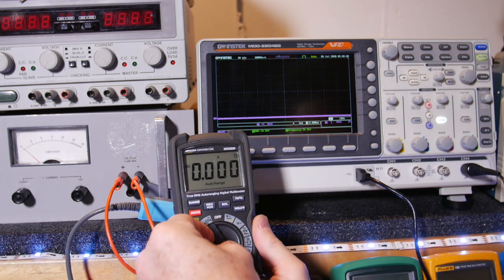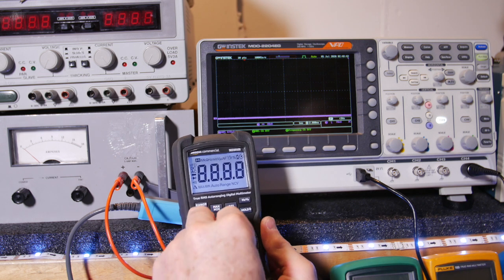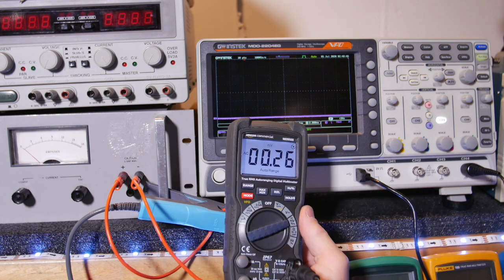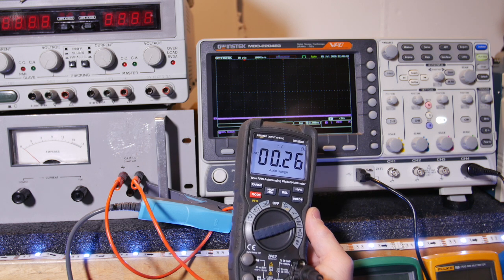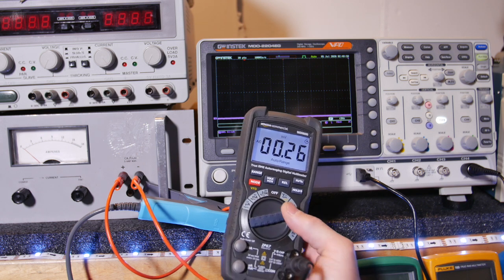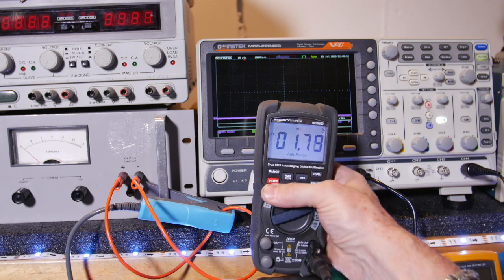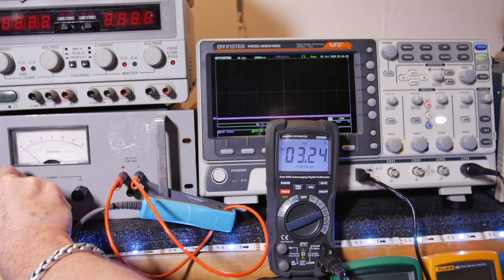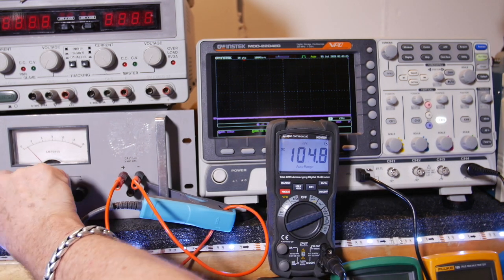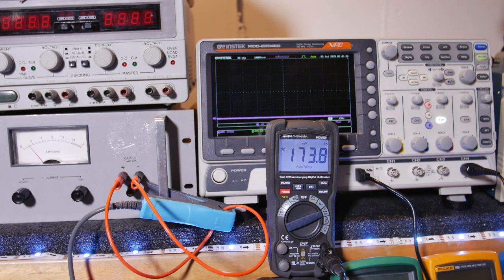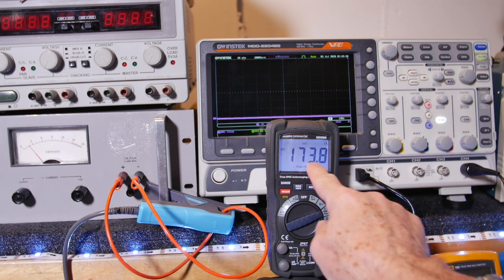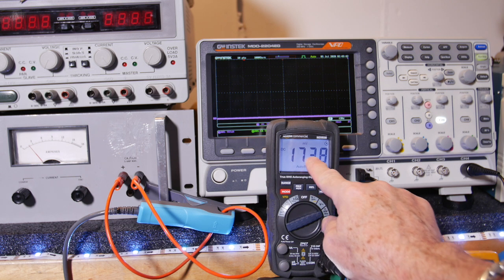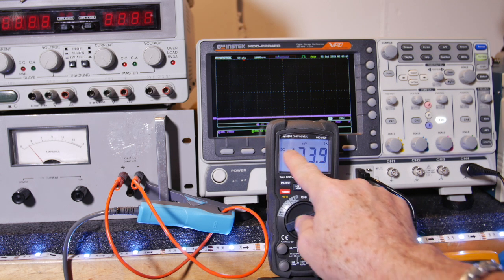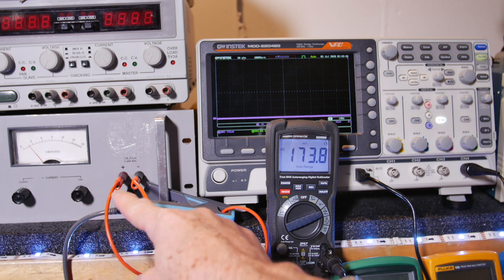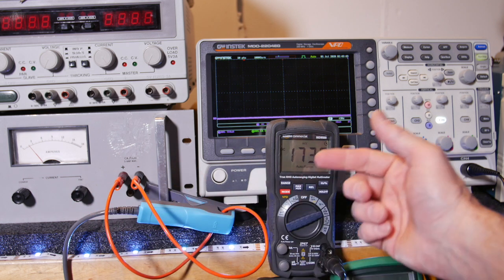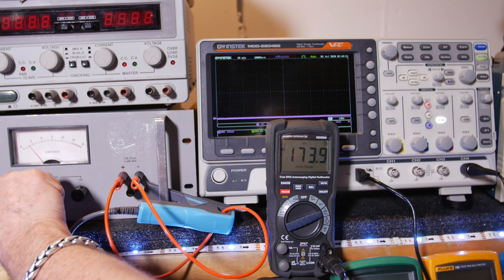Okay, so then come over here to volts. I think it's millivolt range, and look at that, it's 0.26 millivolts. Well, that's AC. Let's see if that's right. Okay, let's go ahead and bring this current up. The Micsig is in times 10 position, so you have to multiply this by 10. So it's saying 173 milliamps, and it's most likely 1.7 amps. Okay, bring it up a little bit higher.